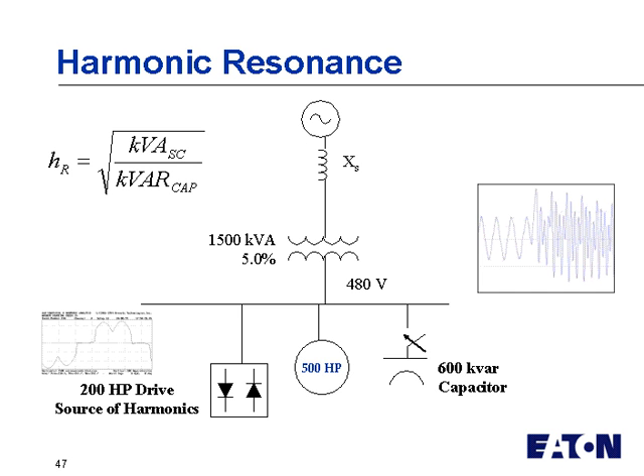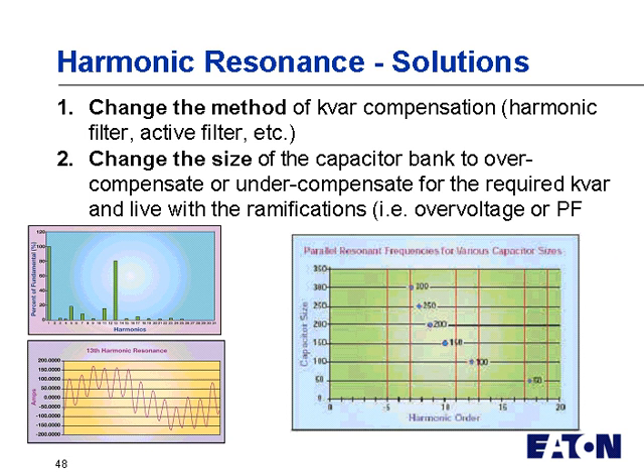And it could amplify the harmonics out of that drive. So for example, if the drive produced 10 amps of 7th harmonic current, you can amplify it to 600 amps flowing back and forth between the capacitor and that transformer. So again, that's why it's self-correcting. You can't have that situation for very long before something fails.